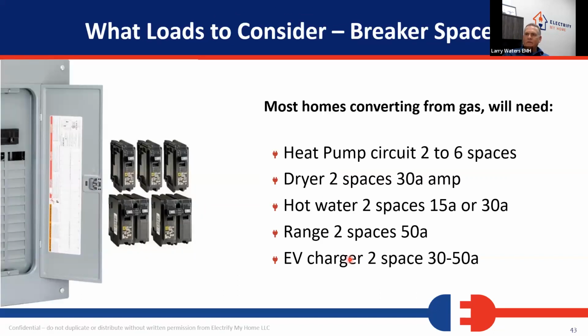Most houses converting from gas will need at least 2 to 6 spaces with a heat pump. This is the big deal right here. A poorly designed or poorly spec'd out heat pump system. And we know, we do a lot of training. We've brought over 100 HVAC contractors to our training in the last year and a half, more than 200 individuals. And there are a lot of companies out there that are offering the low price heat pump solution, which is just basically an inefficient air conditioner by today's standards that runs backwards in the winter to give you heat, but loses a lot of its capacity when it gets cold outside.